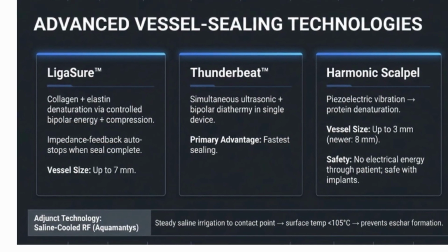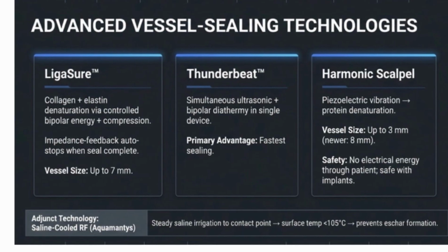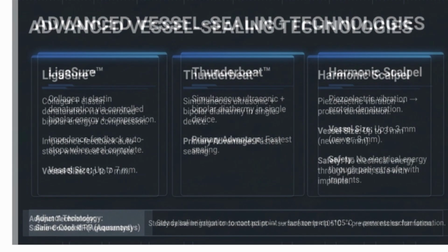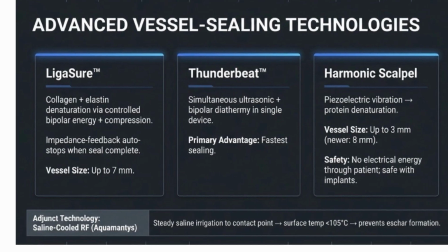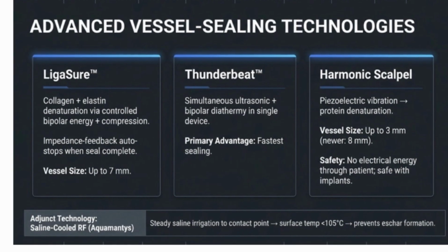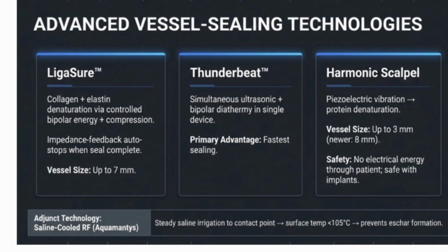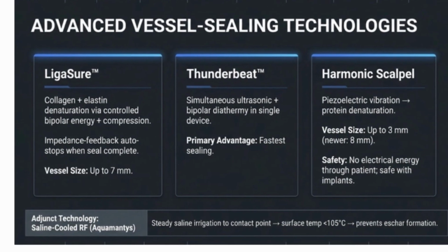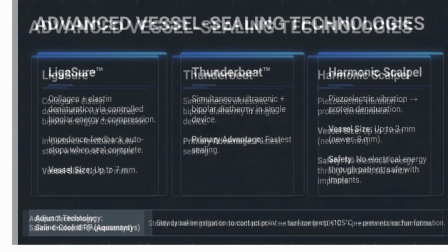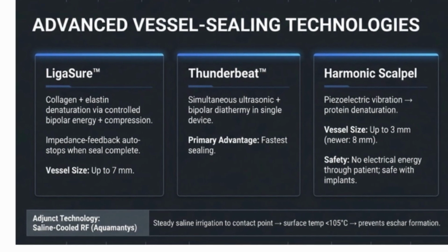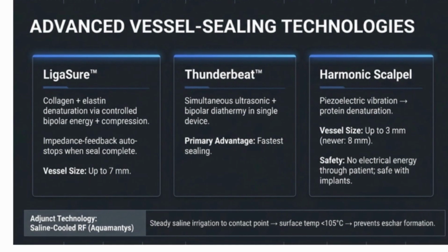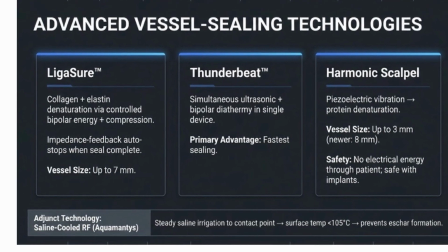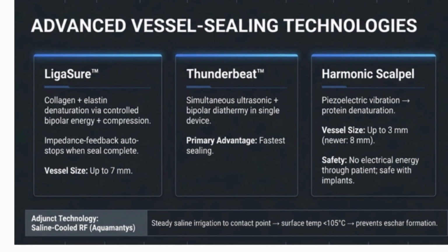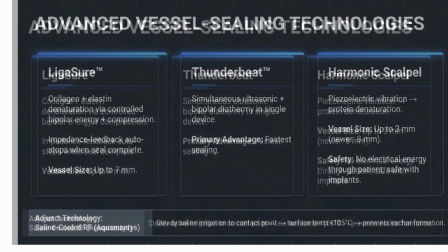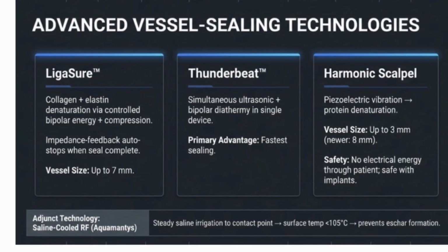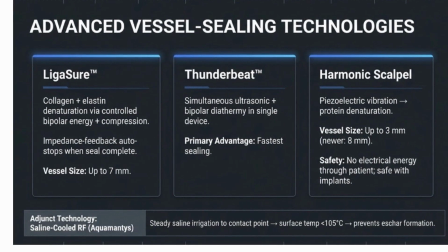The advanced vessel sealing bipolar methods are the LigaSure and saline cooled radiofrequency, Aquamantys, and ultrasonic measures, the harmonic scalpel, and ultrasonic with the bipolar, the Thunderbeat, are also the modes. In bipolar, LigaSure and EnSeal we have already discussed. In saline cooled Aquamantys, there is steady saline irrigation to the contact point, then the surface temperature is less than 105. It prevents eschar formation. In the harmonic, there is ultrasonic energy that causes the protein denaturation. The vessel size is up to 3 mm. There is no electric energy to the patient and it is safe with implants.